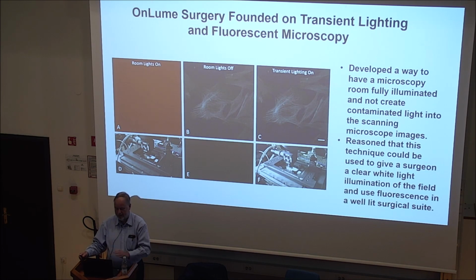The third column is what we call transient lighting. So we're having bursts of light to illuminate the field, but the lights are only on in the raster pattern when the raster scan goes off the edge. There's a time then that the excitation laser is not producing fluorescence anyway, so you might as well turn it off, right? Or turn on the white lights. So you then have these bursts of white lights that the eye can't tell that it's not steady, right? So you can now go work in the microscopy room while you're acquiring the image. And this is basically how it works.